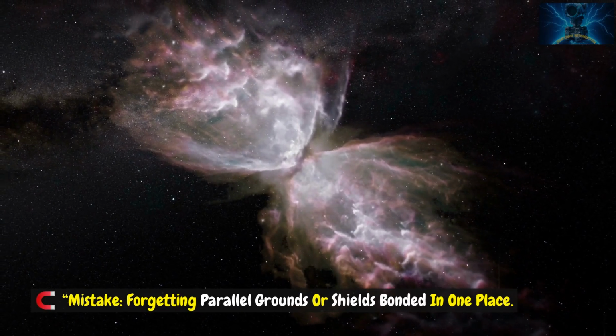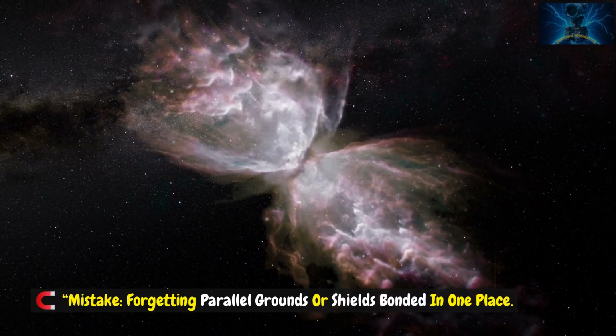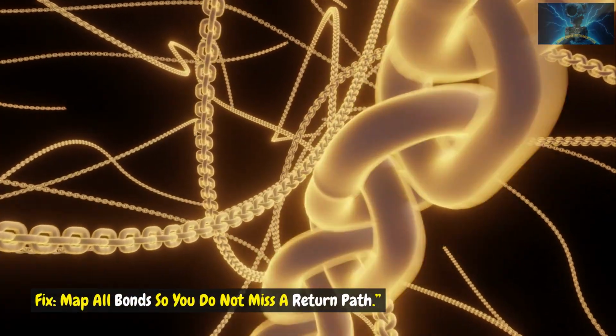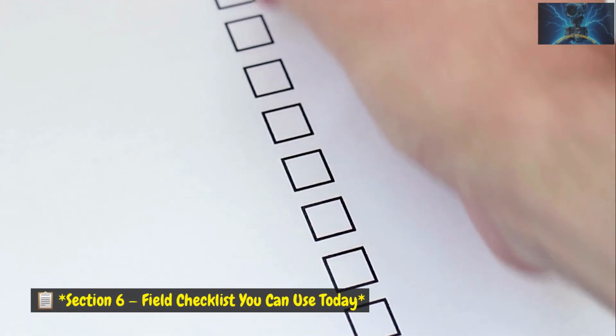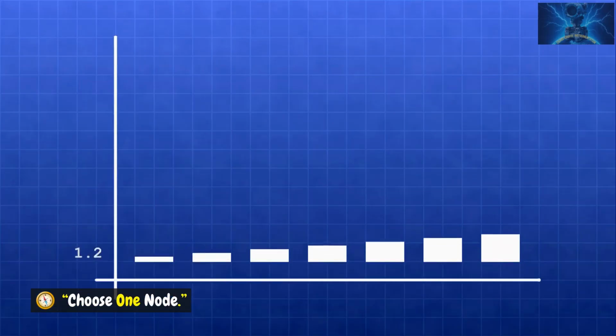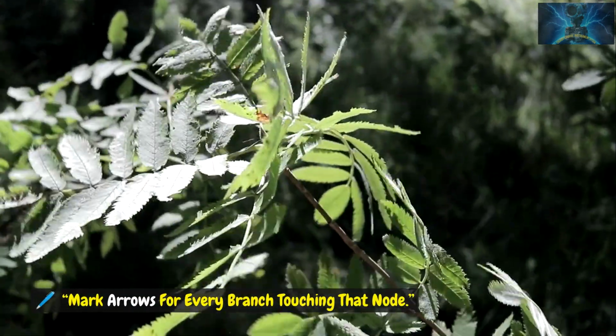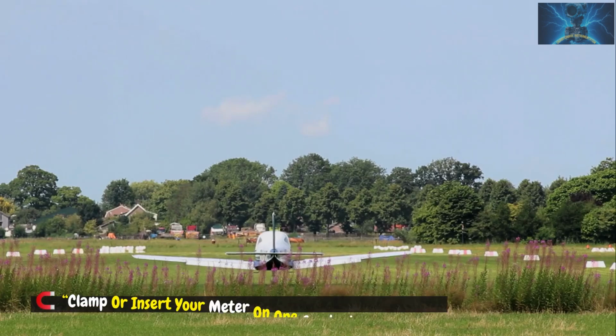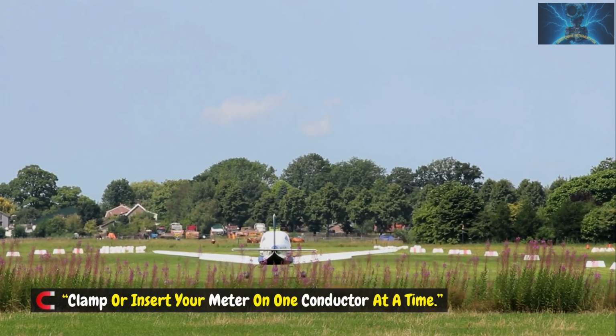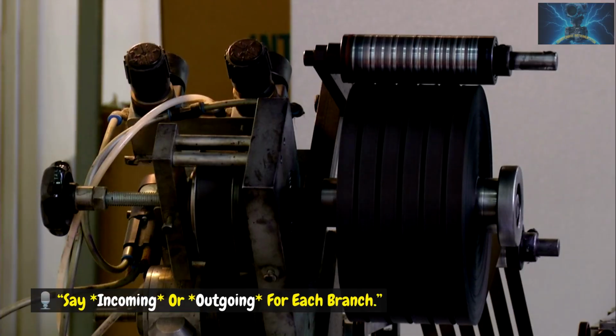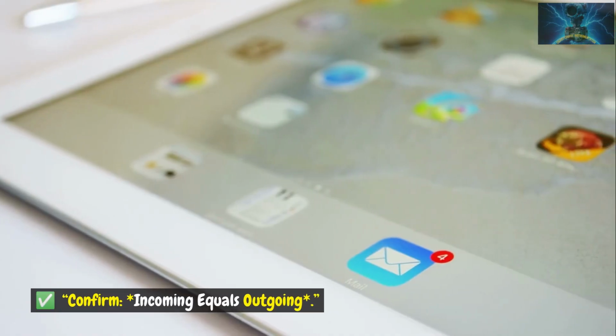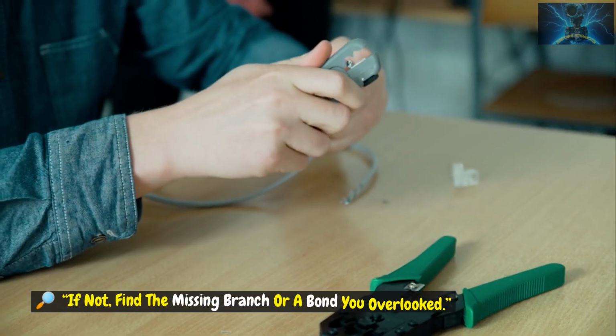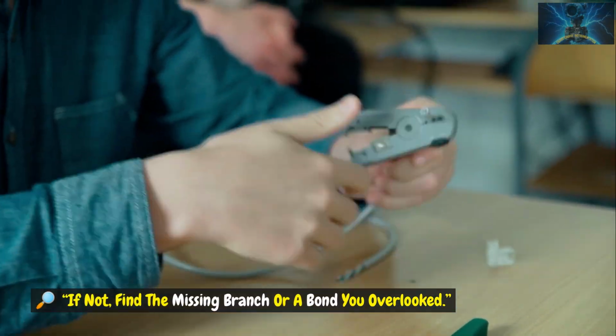Mistake: forgetting parallel grounds or shields bonded in one place. Fix: map all bonds so you do not miss a return path. Section 6. Field checklist you can use today. Choose one node. Mark arrows for every branch touching that node. Clamp or insert your meter on one conductor at a time. Say incoming or outgoing for each branch. Confirm incoming equals outgoing. If not, find the missing branch or a bond you overlooked.